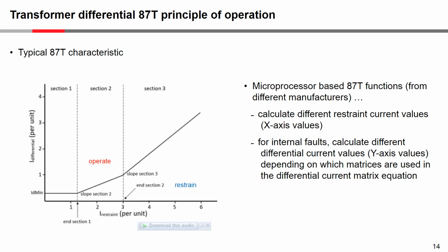Now, this is where we start seeing some differences, because microprocessor-based 87T functions from different manufacturers calculate different restraint current values. So for exactly the same fault, one relay versus another may not put you at the same place on the x-axis. And for internal faults, they can calculate different differential values. What that means is that even where you get located on the y-axis would be different for the same fault.